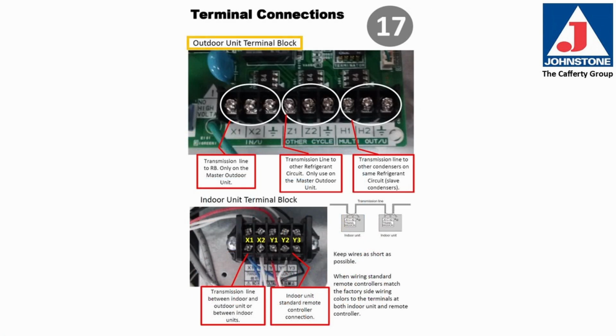Here are the connections on the outdoor unit terminal block. The transmission line to the RB unit, only on the master outdoor unit, connects to X1, X2, and shield. The transmission line to the other refrigerant units, used only on the master outdoor unit as well, connects to Z1, Z2, and shield.